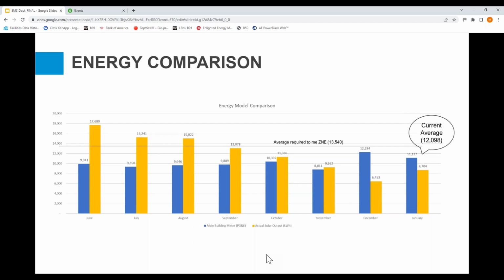One of the other things we do, not shown here, is kind of a net accumulator that says whether we're positive or not. To explain that better, if you look at the month of June, the solar output is much higher than the consumption, and that's great, that's what we'd like to see on a regular basis. But as with most solar systems, when you get into months like December and January, the building consumed more than it produced, and that's pretty typical.